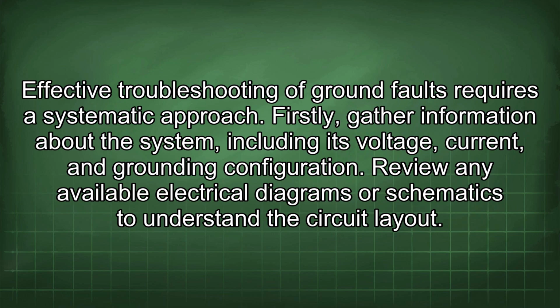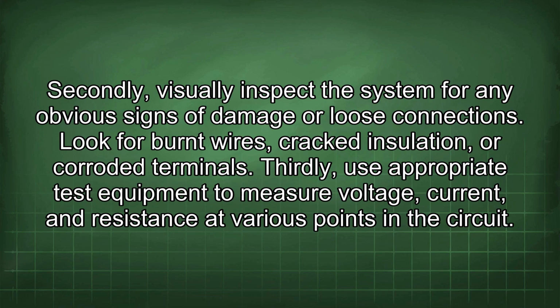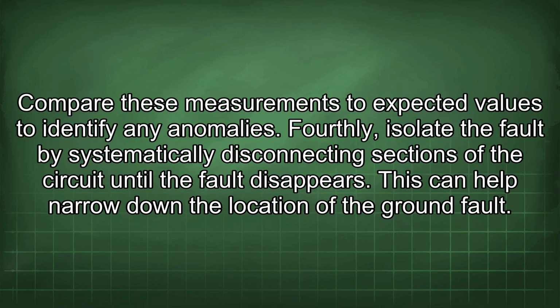Effective troubleshooting of ground faults requires a systematic approach. Firstly, gather information about the system, including its voltage, current, and grounding configuration. Review any available electrical diagrams or schematics to understand the circuit layout. Secondly, visually inspect the system for any obvious signs of damage or loose connections. Look for burnt wires, cracked insulation, or corroded terminals. Thirdly, use appropriate test equipment to measure voltage, current, and resistance at various points in the circuit. Compare these measurements to expected values to identify any anomalies.